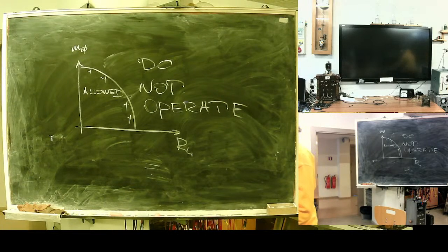And who is this? A transformer. Yes, it's a transformer. I can turn it like this. This one is for 10 kilovolts. But why, what's going on in it? See? Two cores. Why? One is more massive, from quite raw sheets. This one has quite fine steel in it, and it's much smaller. This one is for metering, and this one for protection. This one for precision. This one for robustness. It can take a much higher current load.